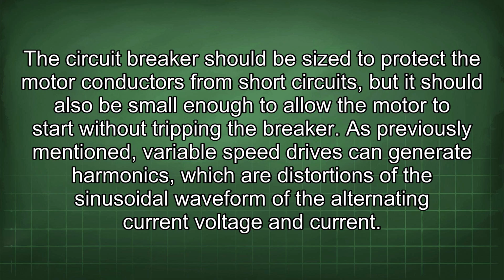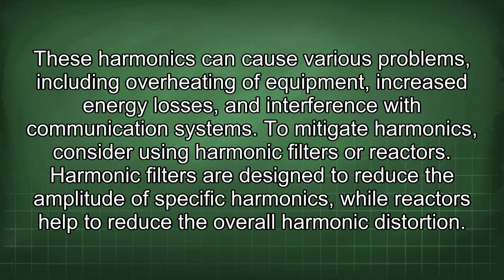As previously mentioned, variable speed drives can generate harmonics, which are distortions of the sinusoidal waveform of the alternating current voltage and current. These harmonics can cause various problems, including overheating of equipment, increased energy losses, and interference with communication systems. To mitigate harmonics, consider using harmonic filters or reactors. Harmonic filters are designed to reduce the amplitude of specific harmonics, while reactors help to reduce the overall harmonic distortion.